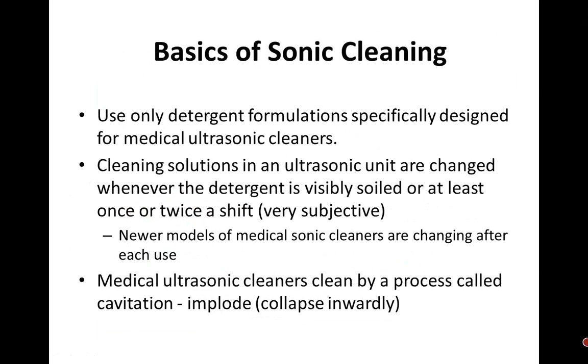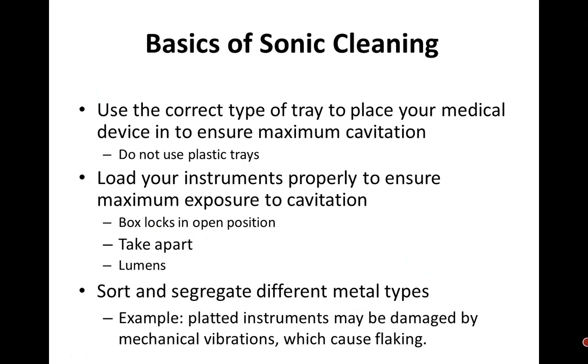And you need to understand that when you're buying a new sonic cleaner, newer models are changing every time. Medical ultrasonic cleaners clean by a process called cavitation: imploding, not exploding. So the use of the correct type of tray is very, very important. Plastic will tend to absorb the energy, so you don't want to use plastic trays because it will decrease the cavitation and its reaching the instruments.